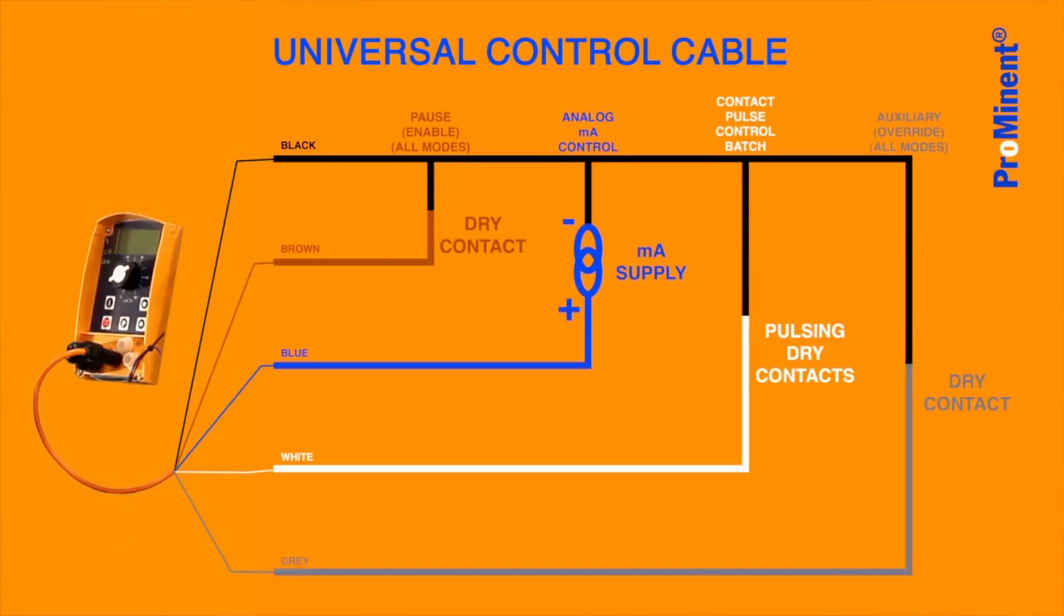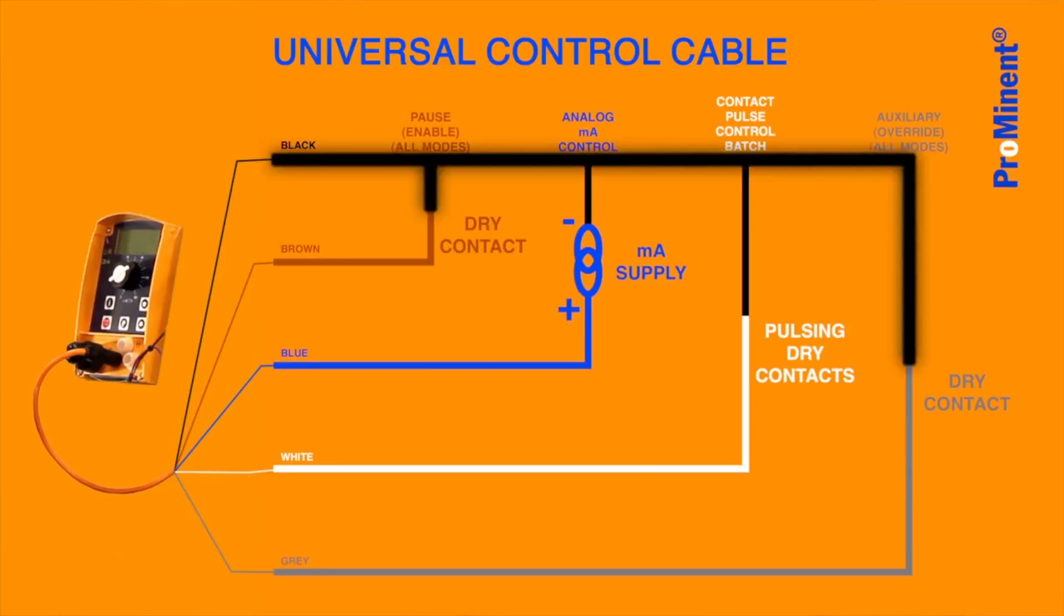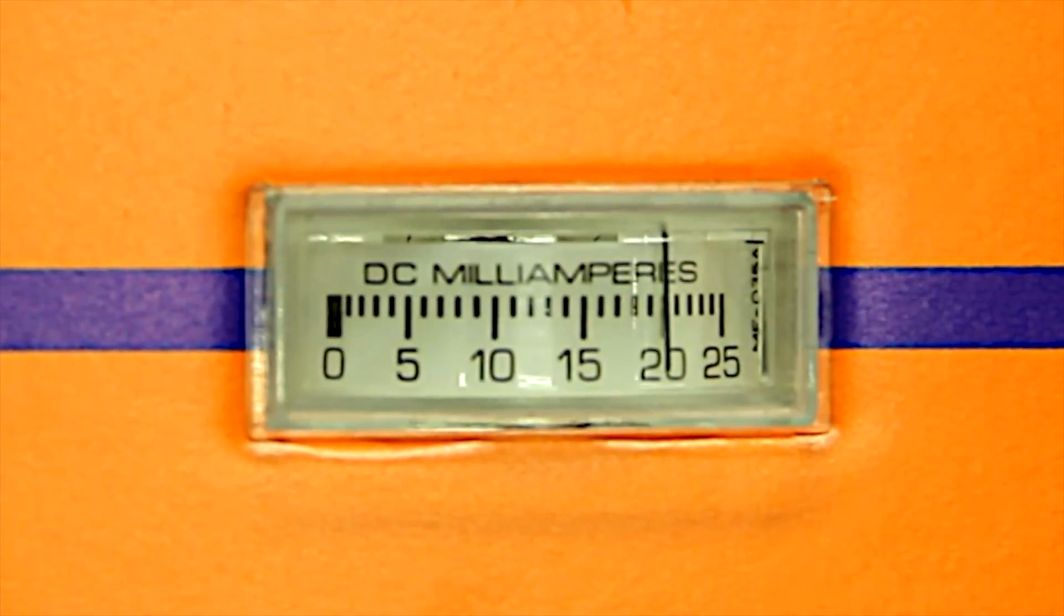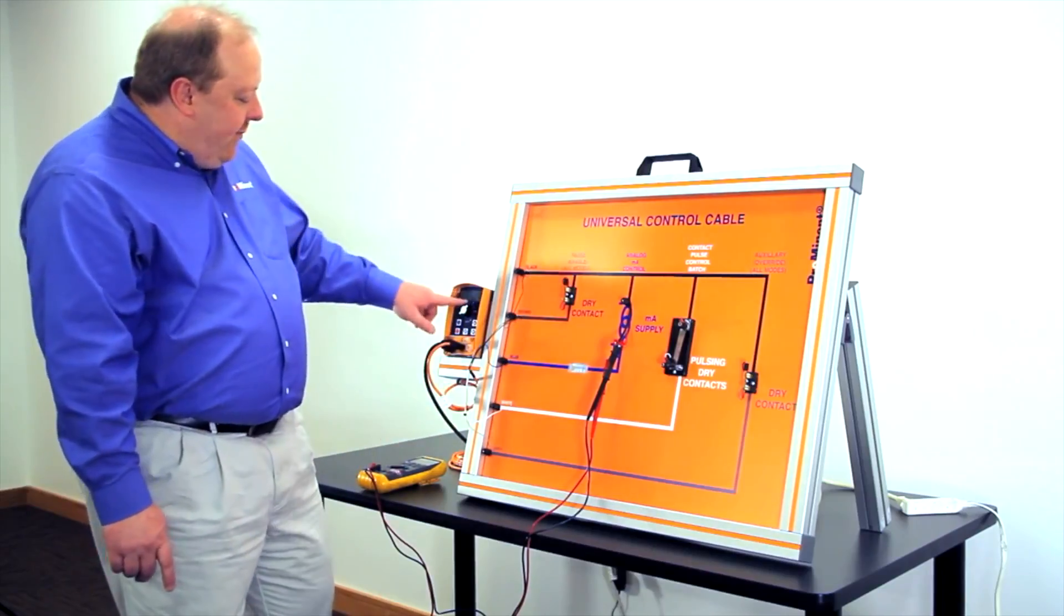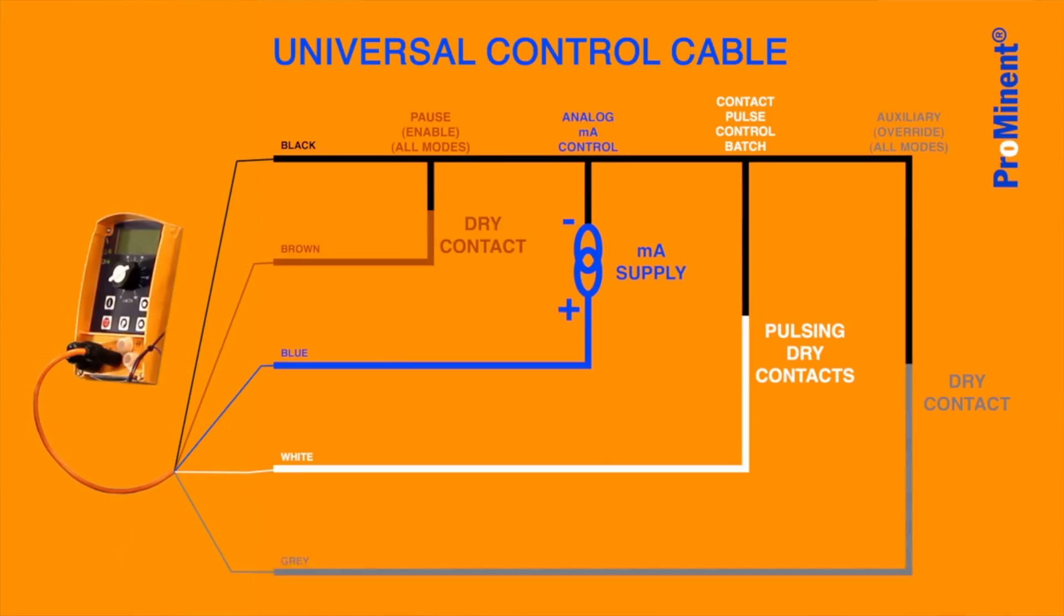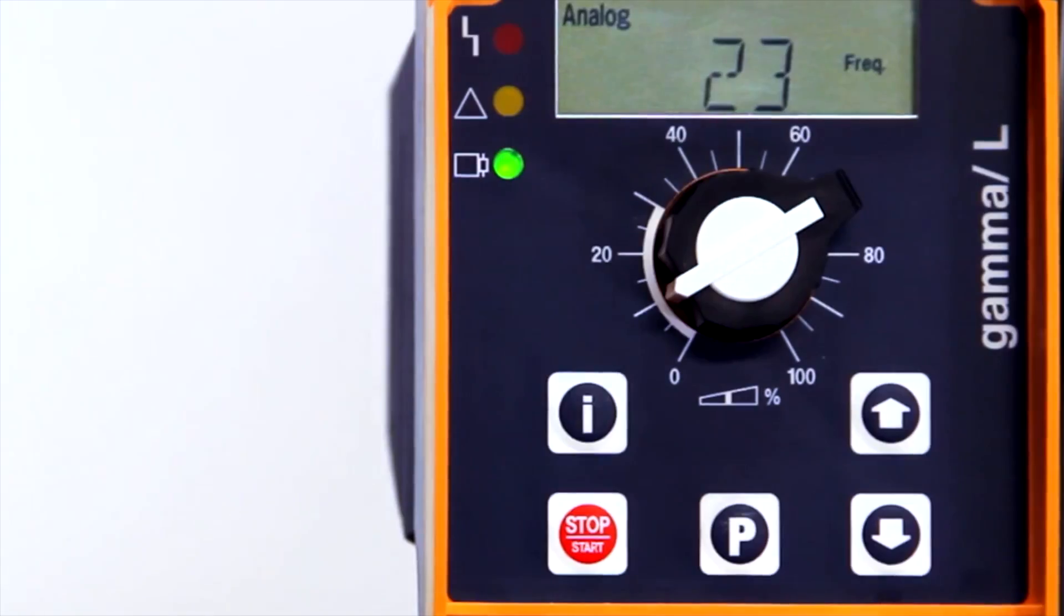When we short the gray wire here to the black wire, which again is made to the brown wire, it's going to override our current signal, which is telling the pump to run at its maximum speed, and we run at this predetermined frequency. Here we predetermined that we wanted, once the gray wire is made to the black wire through again a dry contact, we want the pump to run at 23 strokes per minute.